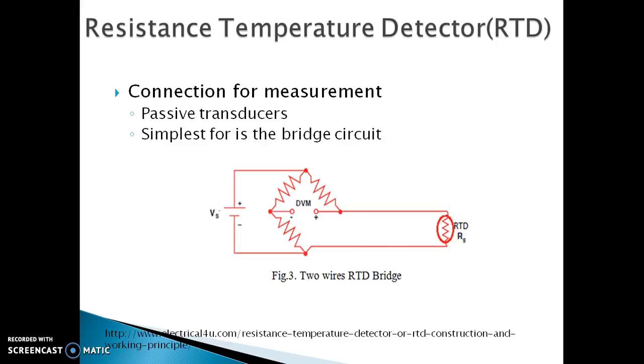Let's look at what is a bridge circuit. A bridge circuit is a simple circuit for measuring an unknown resistance by connecting it to the three known resistances in the circuit and giving a voltage source. By supplying the constant electric current and measuring the voltage, the RTD resistance can be calculated.